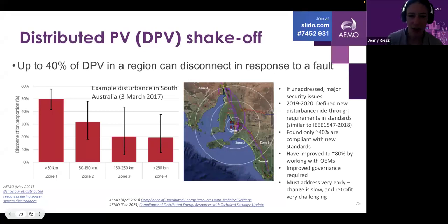So firstly, this underpinning capability of disturbance ride-through, we discovered this. This is actually one of the original examples that we discovered back in 2017. There was, in South Australia again, a series of explosions at one of our large gas-fired power stations, which led to voltages dropping very low right in the middle of the main capital, Adelaide, where there is a very large concentration of distributed PV.